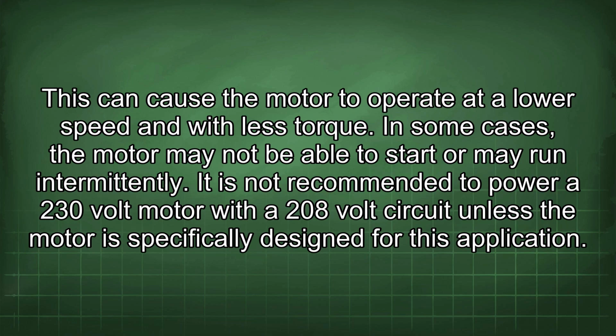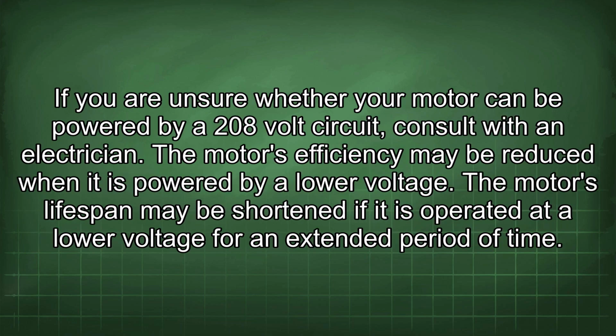This can cause the motor to operate at a low speed and with less torque. In some cases, the motor may not be able to start or may run intermittently. It is not recommended to power a 230-volt motor with a 208-volt circuit unless the motor is specifically designed for this application. If you are unsure whether your motor can be powered by a 208-volt circuit, consult with an electrician. The motor's efficiency may be reduced when it is powered by a lower voltage. The motor's lifespan may be shortened if it is operated at a lower voltage for an extended period of time.